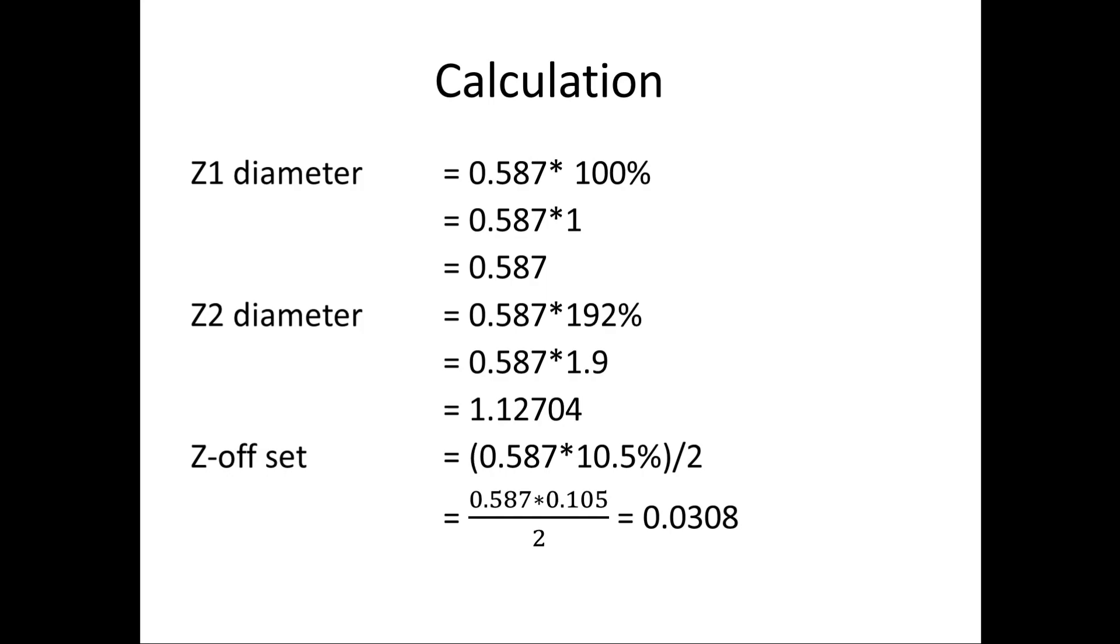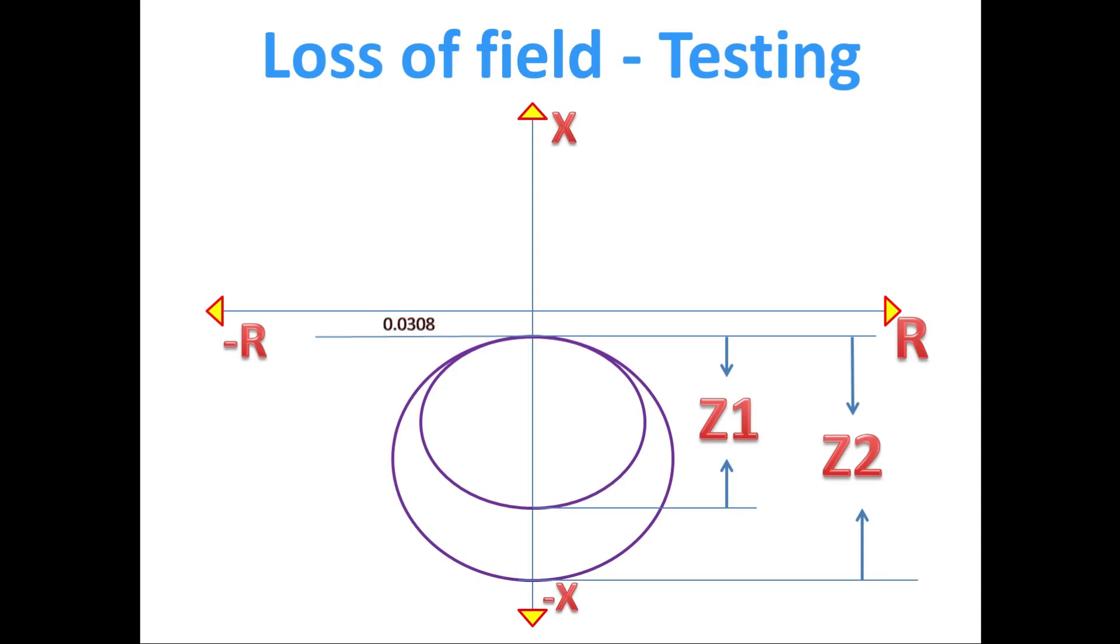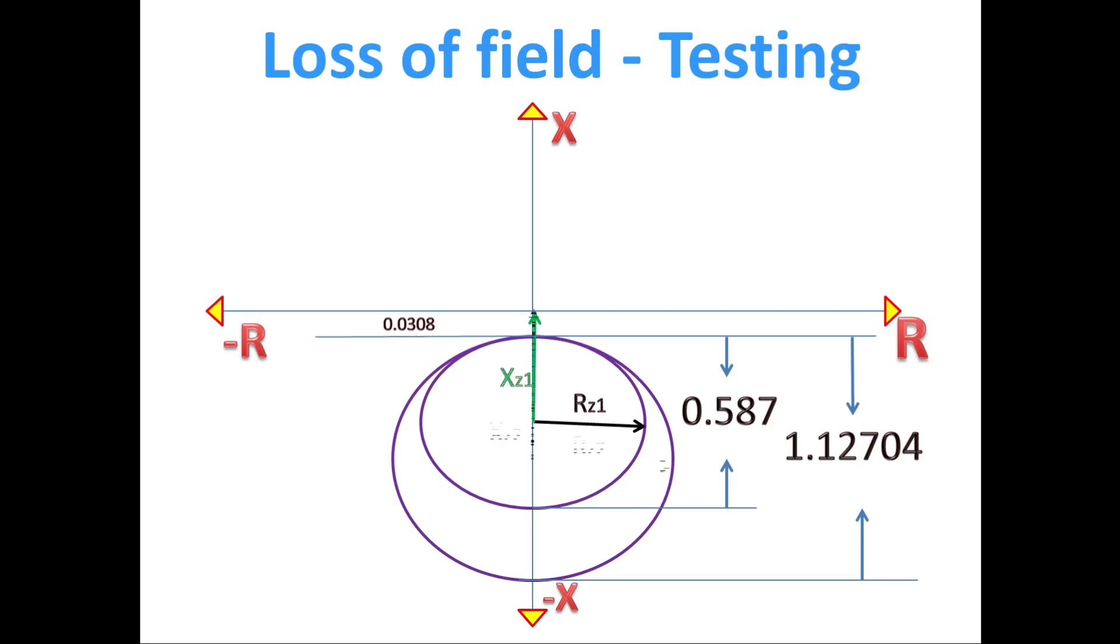For these above calculated values, we are going to draw the mho characteristics. Z1 diameter is 0.587 and for Z2 diameter is 1.12704. We have the diameter of the circle, from that we can find X and R value.